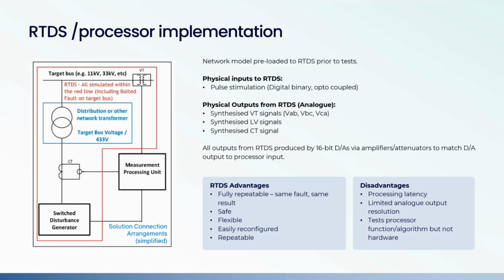The computer can also model the high voltage, high current section of the RTFLM, all that's within the red line on the diagram, all the area within the red line. And that just leaves outside the red line the measurement processing unit, the RTFLM processor. And that's the real bit of hardware, the bit that's included in the loop. The processor behaves exactly as it does in the full hardware system, and it doesn't know that it's being talked to or being replied to by a computer. It thinks it's in a network.